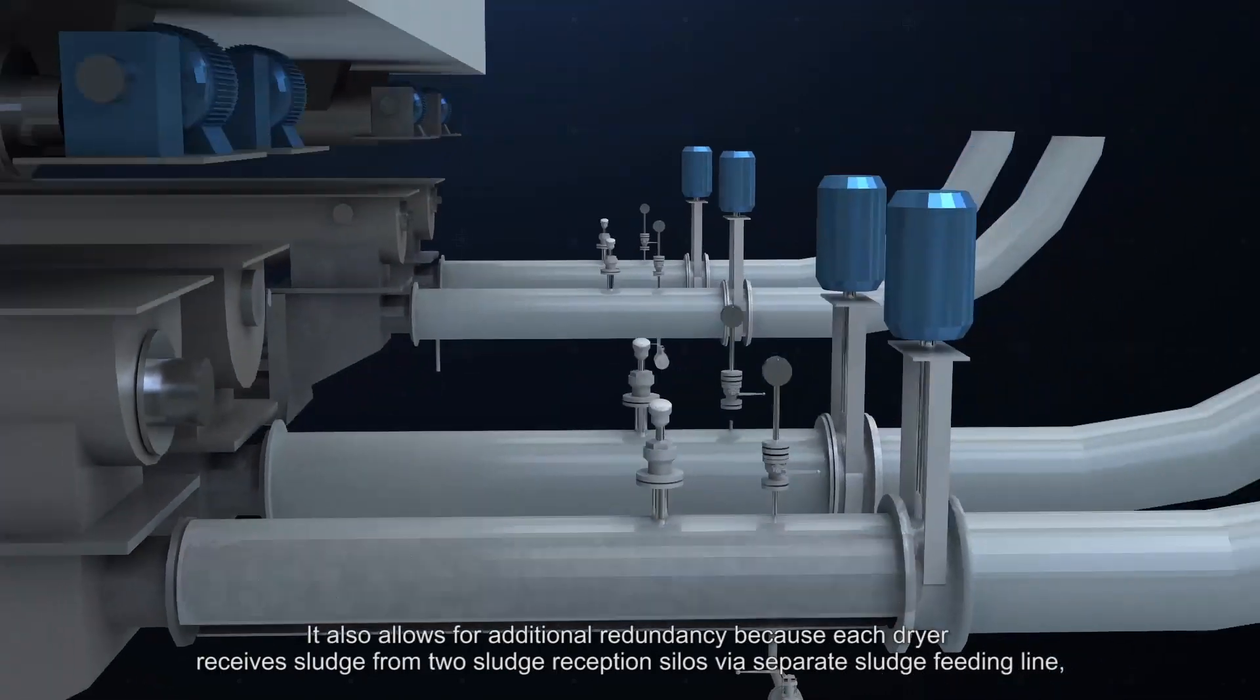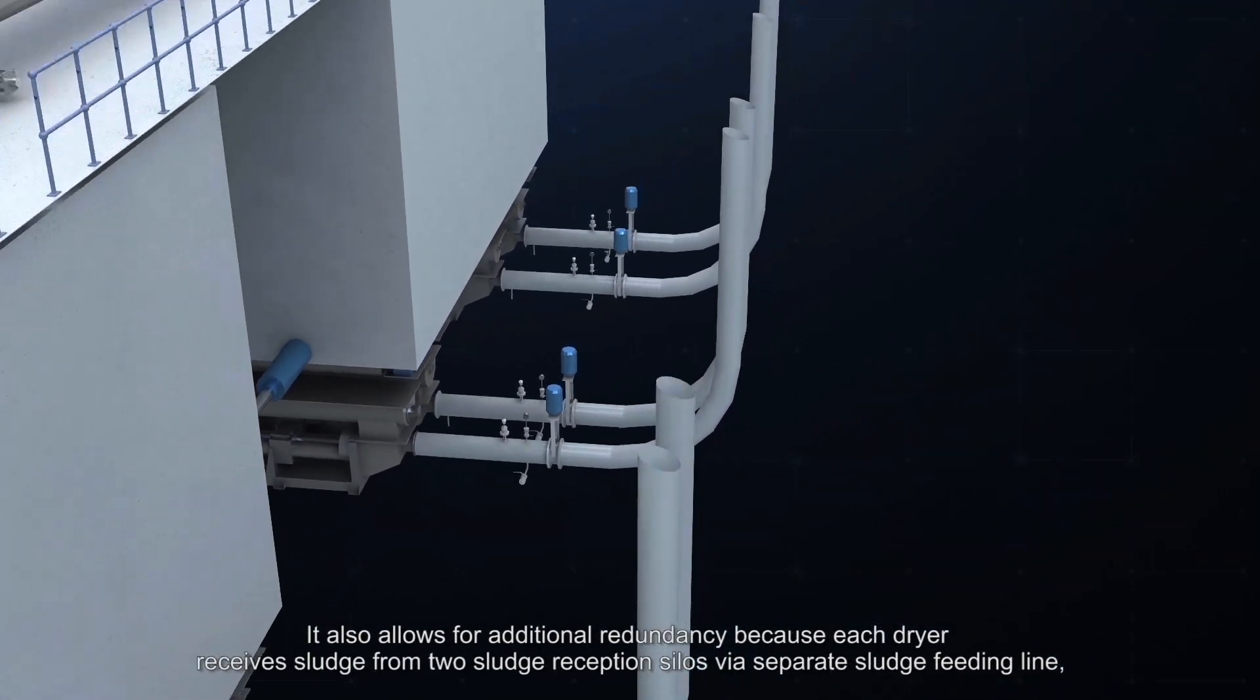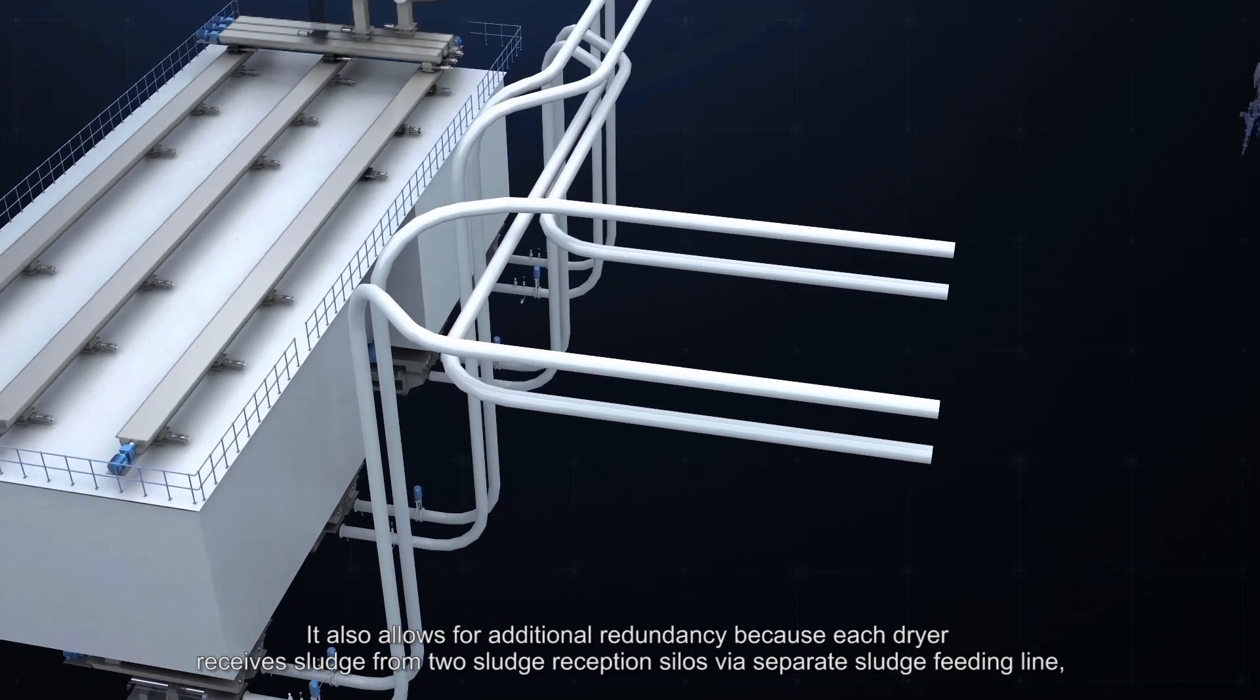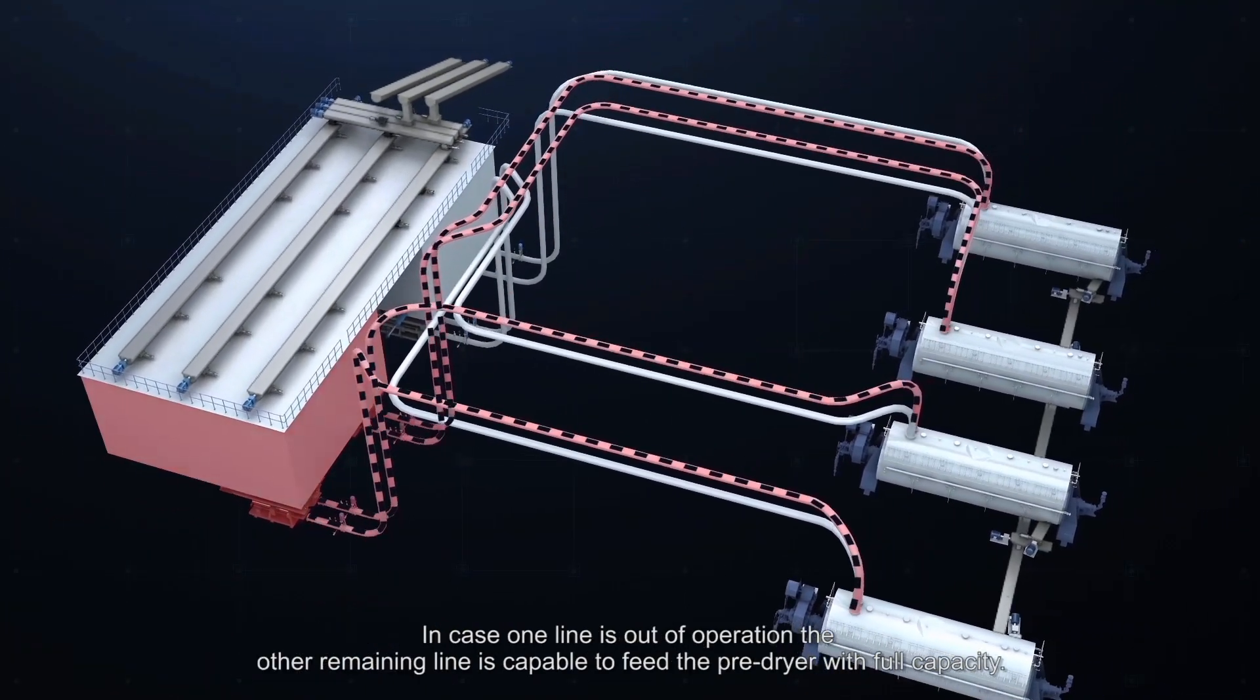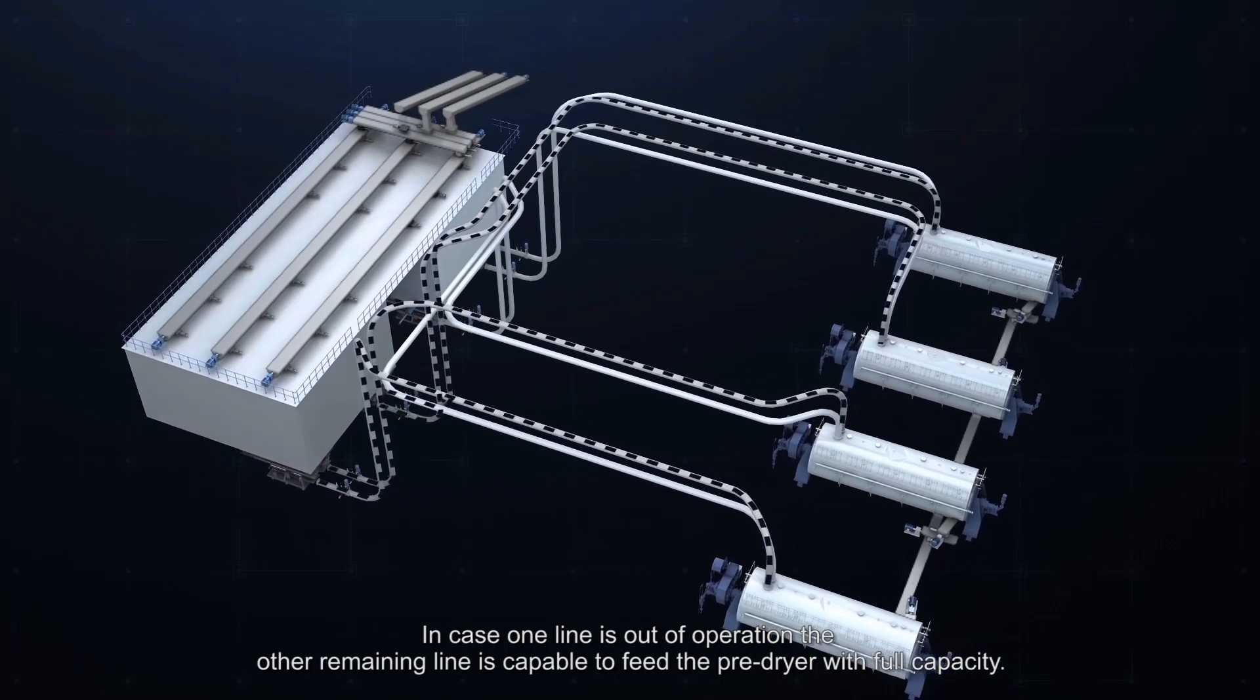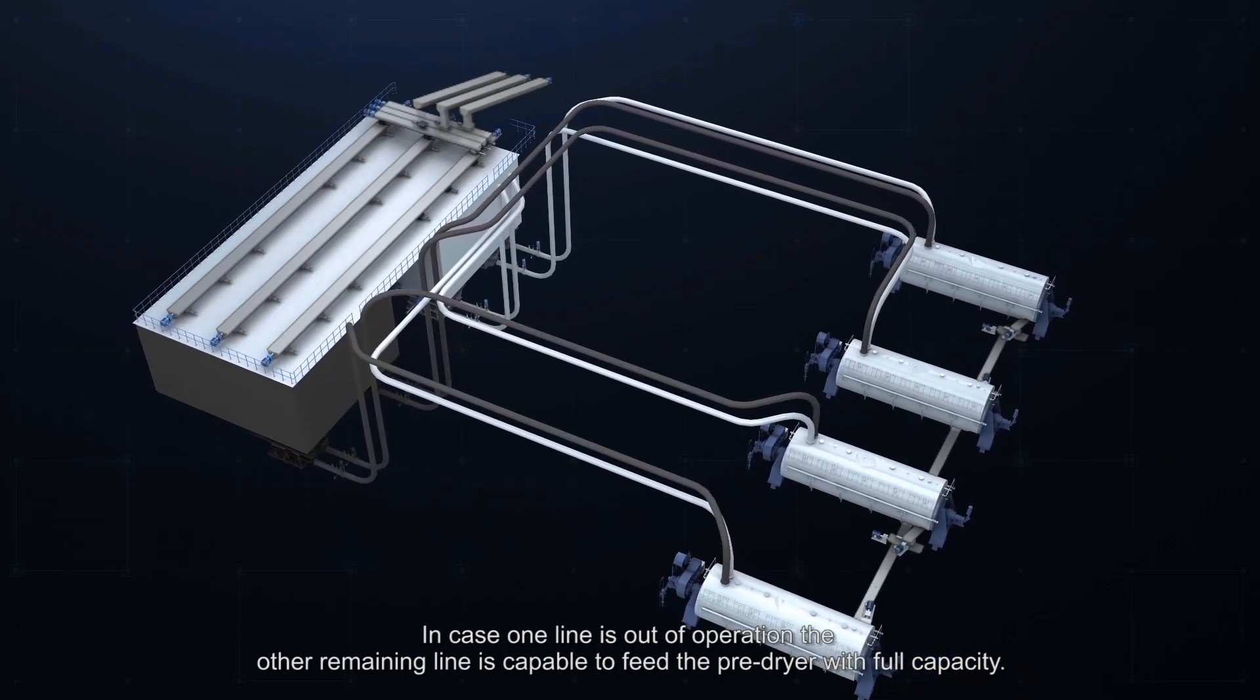It also allows for additional redundancy because each dryer receives sludge from two sludge reception silos via separate sludge feeding line. In case one line is out of operation, the other remaining line is capable to feed the pre-dryer with full capacity.